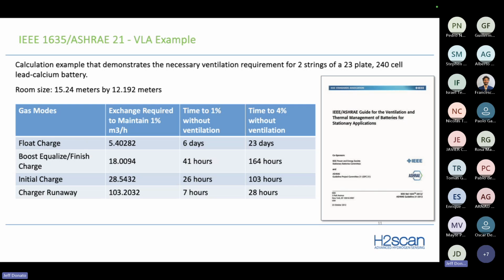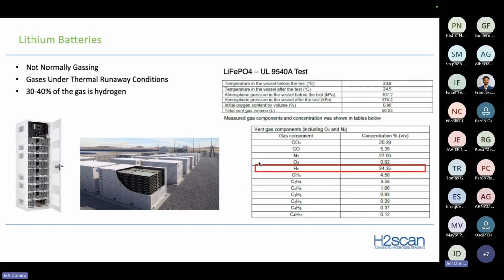So you don't need a very fast sensor. I would say that most of the sensors out there today meet the specifications for making sure you mitigate under normal circumstances. And then of course, for boost, equalize, charge, it's 41 hours in their particular case for 1%, and then 164 hours to reach 4%. So a very, very slow buildup of hydrogen. So there's a lot of time to activate your mitigation plan if something were to happen.